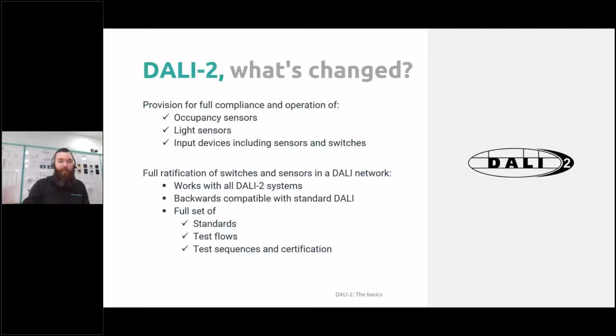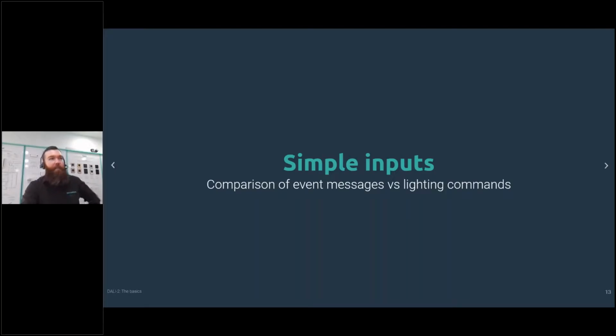The really exciting thing in DALI 2 is that now we can actually standardize. We can take an occupancy sensor from manufacturer A and an occupancy sensor from manufacturer B and use them together on the same system with the same application controller. So that's great, and we're going to talk a little bit about how it does that as well.